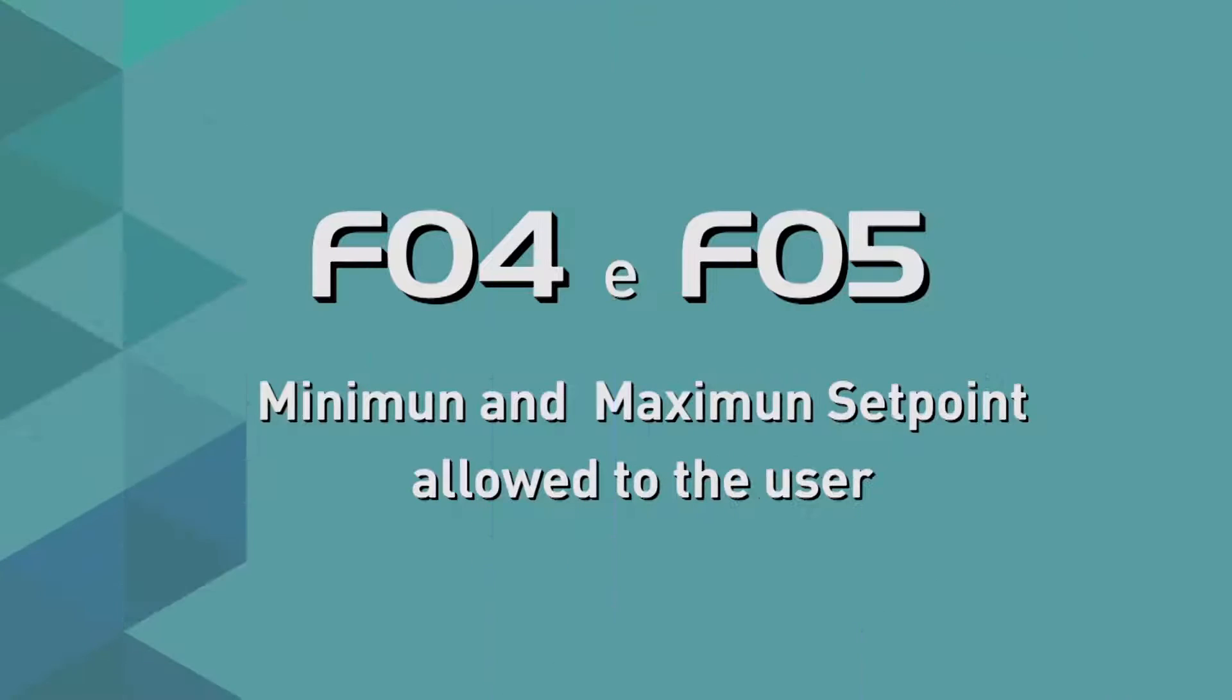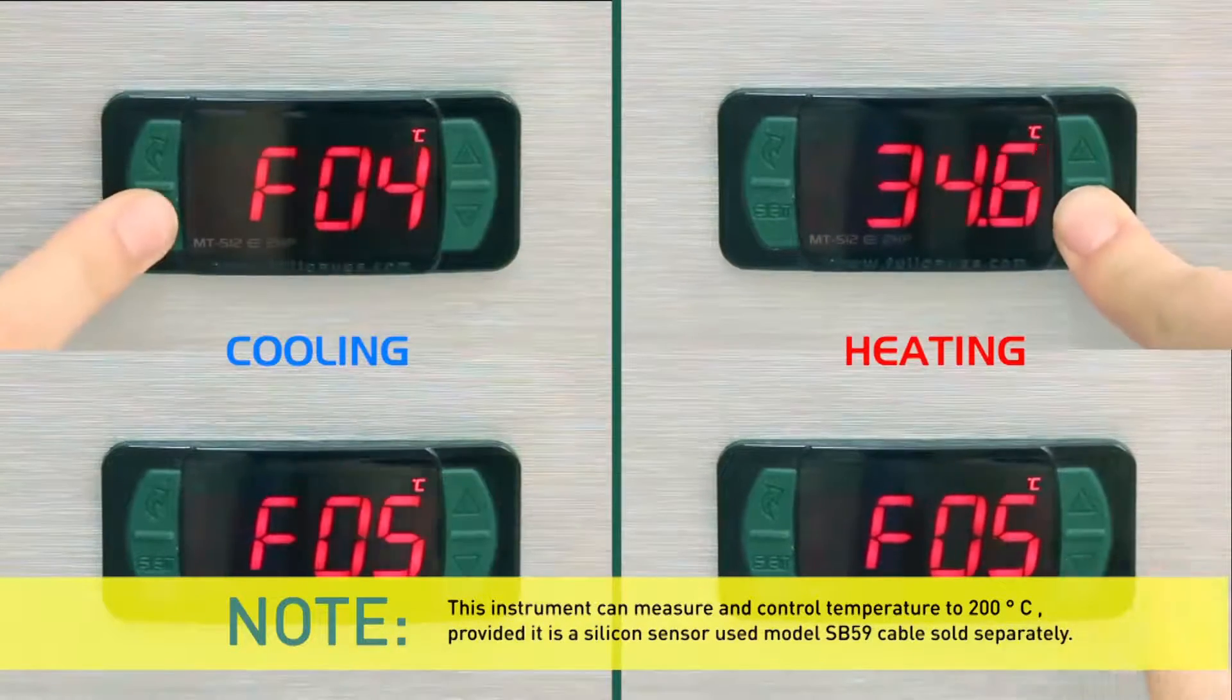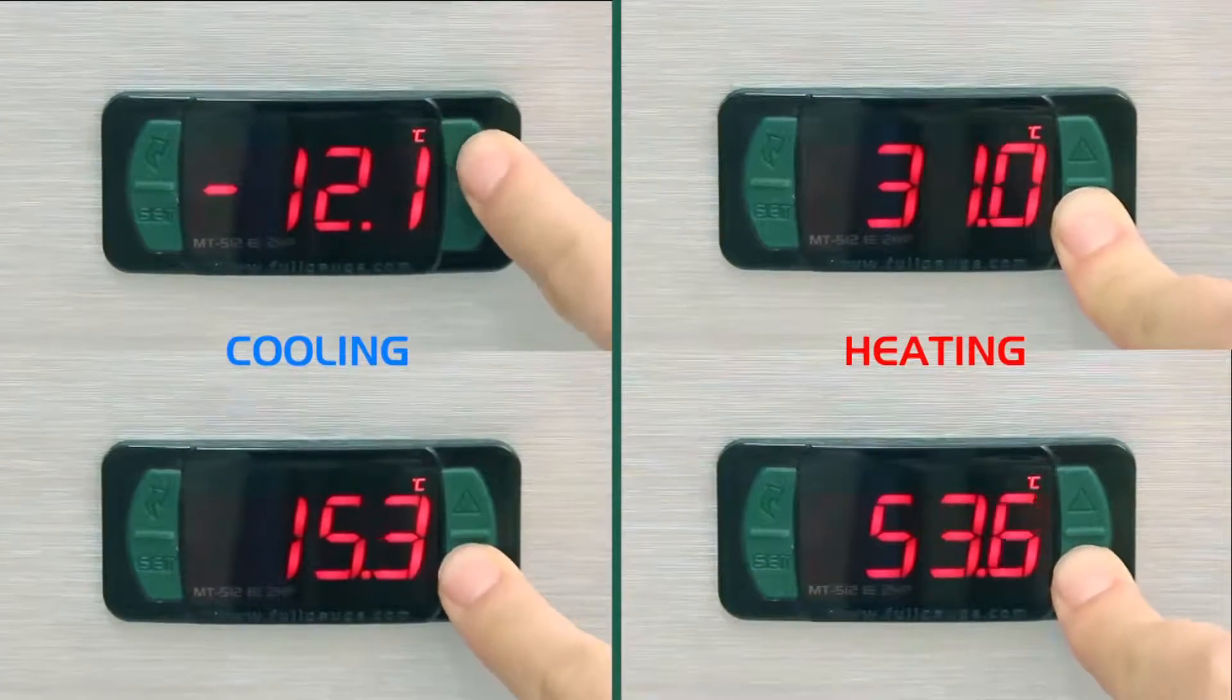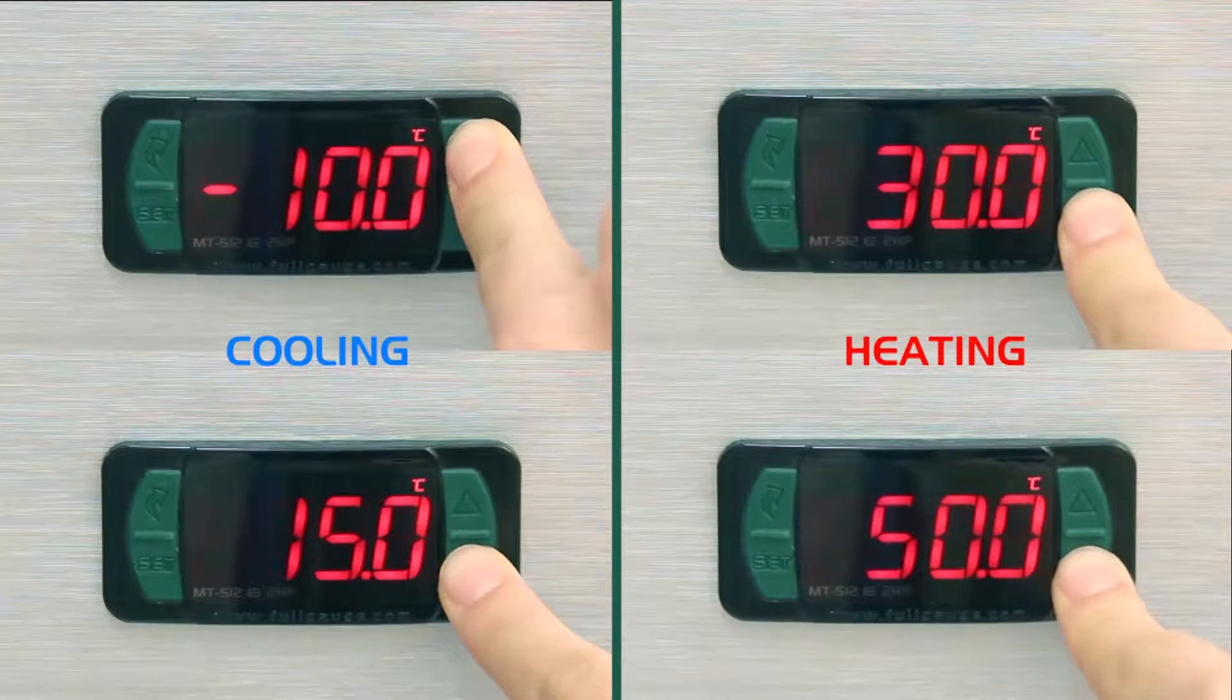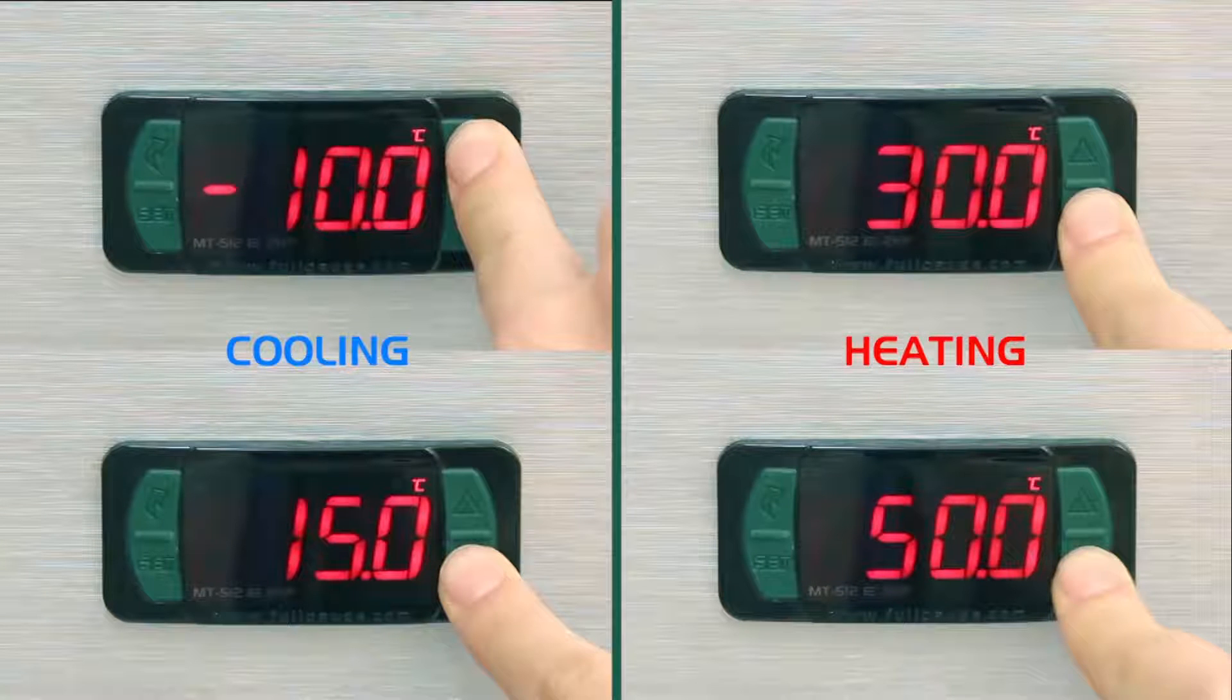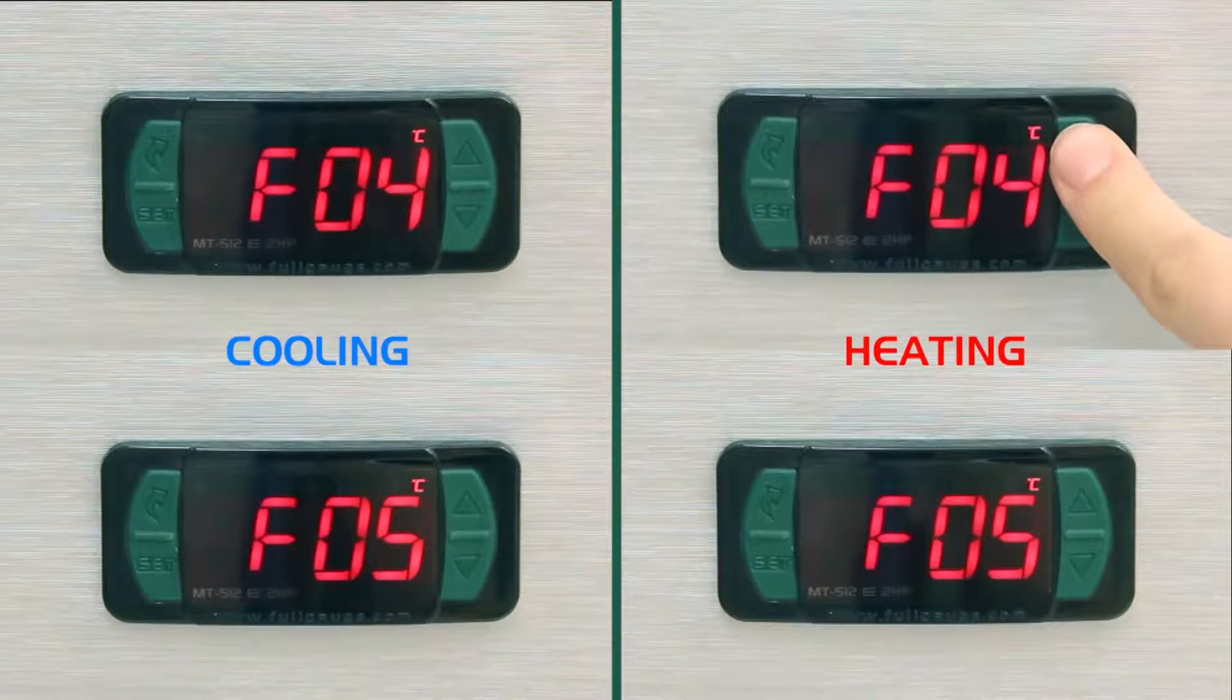F04 and F05. Minimum and maximum set point allowed to user. The MT512E2HP controller can control temperatures within a range of minus 50 to 105 degrees Celsius. In the examples, we limit this range to minus 10 to plus 15 degrees Celsius in cooling and 30 to 50 degrees Celsius in heating. These limits, or electronic stops, restrict the range released to adjust the set point, seeking protection and security.